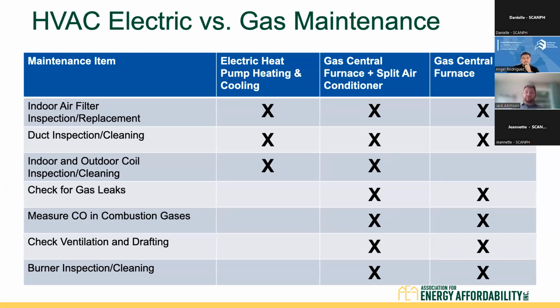And then the benefit of having an all-electric HVAC is you can remove all of these specific gas maintenance requirements. So checking for gas leaks, measuring carbon monoxide in combustion gases, checking ventilation and drafting. You don't need to worry about whether the unit is backdrafting or not. And then burner inspection / cleaning. That's sort of equivalent to the indoor and outdoor coil inspection / cleaning. So that's pretty much the same approach. So it's very similar. And so as you can see, all electric, even though it's different, it's the same as air conditioning. It's just we have less items that we need to maintain for heat pump HVAC.